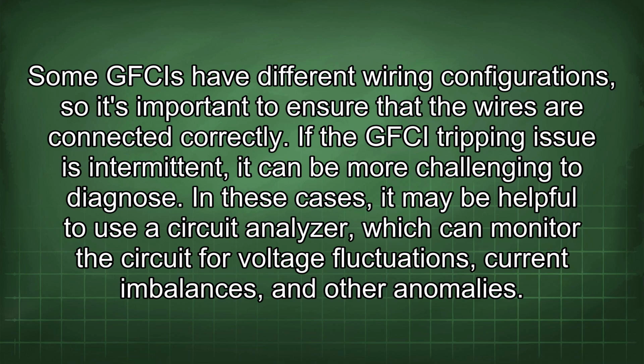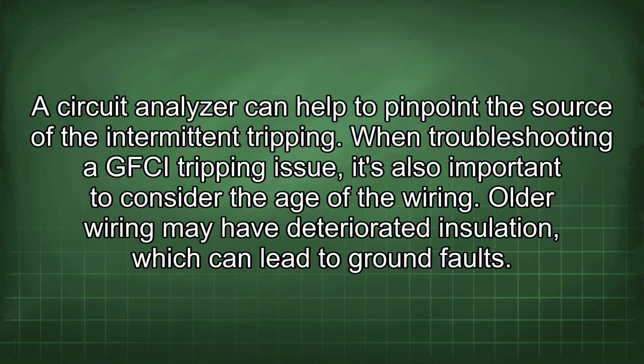If the GFCI tripping issue is intermittent, it can be more challenging to diagnose. In these cases, it may be helpful to use a circuit analyzer, which can monitor the circuit for voltage fluctuations, current imbalances, and other anomalies. A circuit analyzer can help to pinpoint the source of the intermittent tripping.